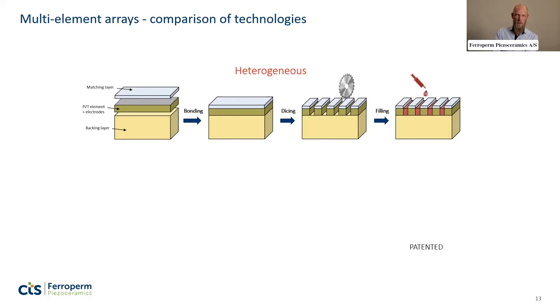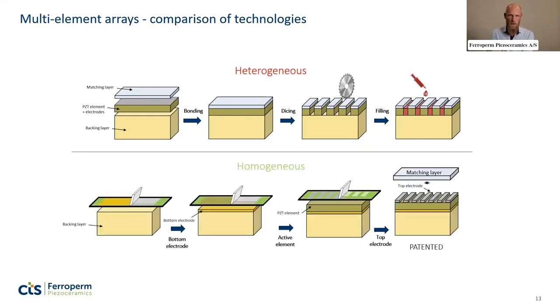And then usually there's a dice and fill processing step as well. So this works quite well. It has some limitations in terms of assembly and costs. So the alternative that we're proposing is to do everything by printing and using thick film technology. So instead of having an assembly process, you basically print the various layers on the substrate or the backing layer, similar to the single element high frequency transducer. And the benefit of that is that, in principle, you can print on any kind of curved substrate using pad printing. You can also print on a flat substrate, and you can pattern the different layers just by the design that you want. So a lot less machining processes involved.